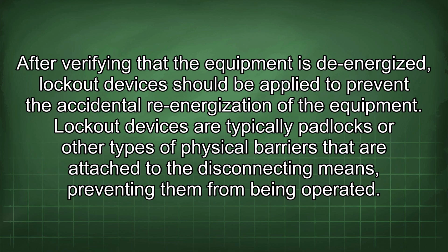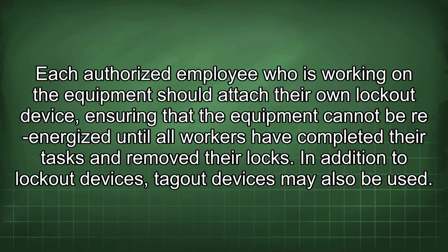After verifying that the equipment is de-energized, lockout devices should be applied to prevent the accidental re-energization of the equipment. Lockout devices are typically padlocks or other types of physical barriers that are attached to the disconnecting means, preventing them from being operated. Each authorized employee who is working on the equipment should attach their own lockout device, ensuring that the equipment cannot be re-energized until all workers have completed their tasks and removed their locks.